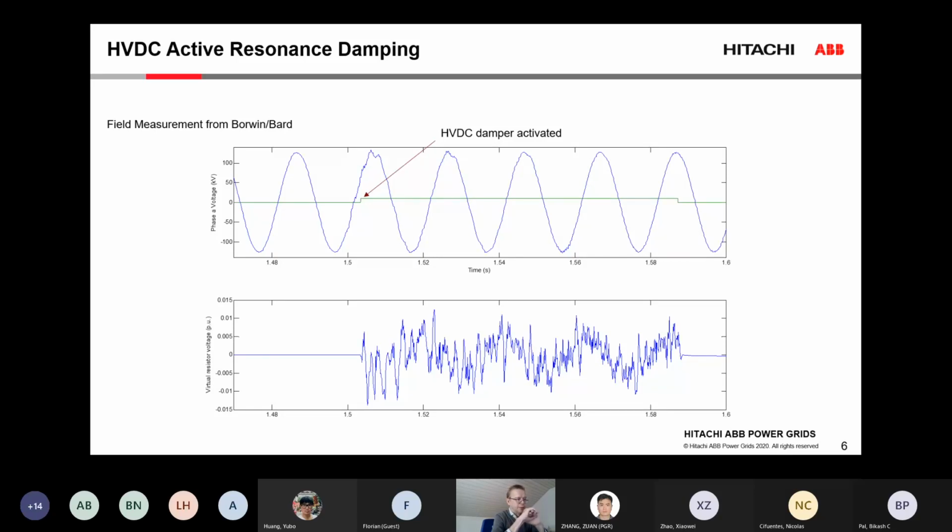And so the problem then is that you would have losses, with about 1.5 or 2 kiloamps rated current. So you would get several megawatts of losses in that resistor. When you do this with active damping, that energy will be taken out of the resonance on the collector grid side, but it will be fed onto the DC link. And then it comes out the German end of the HVDC link as power that they can sell.